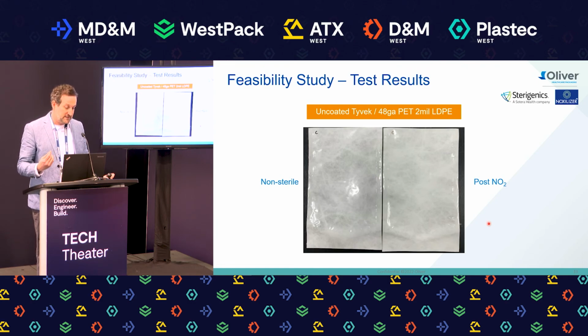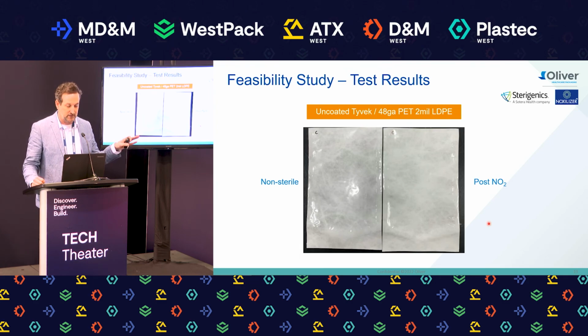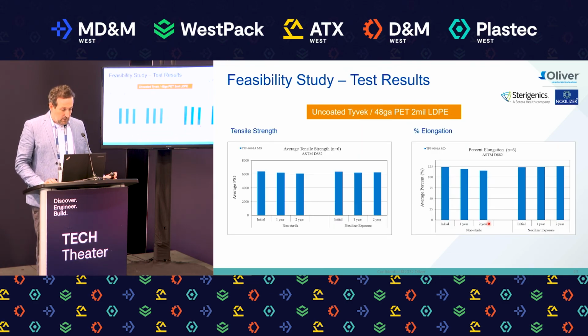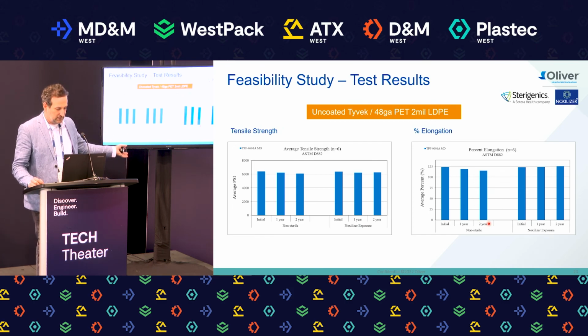So first is the uncoated Tyvek to 48 gauge polyester with a 2 mil low density polyethylene sealant layer. And these are pictures of non-sterile on the left and post NO2, the 2 times cycle, on the right. So again, pre-sterile or non-sterile on the left, Noxilizer exposure on the right. We have tensile strength testing. We have elongation, the same test. You're just pulling the material. We did this test on the polyester side of the pouch for this one, and again, all good results. Tensile strength looked good. The elongation ended up being good.